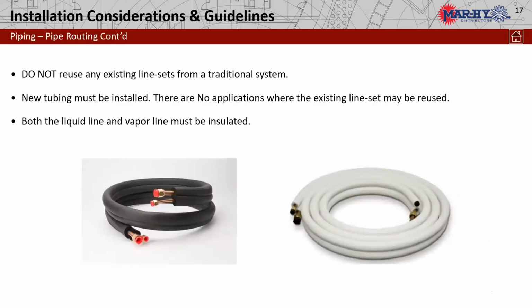Line sets. Do not reuse any existing line sets from traditional systems. Chances are the sizings are not going to be correct. And who's to know what kind of contaminants lay in the traps of the existing line sets. And we don't want to start a new system off with something already contaminated on a startup. We want new tubing installed, and there is no application where an existing line set may be reused. And both the liquid line and the vapor line must be insulated. Such as a mini split, we have both liquid and gas in that liquid line. So it has to be insulated or it will condensate.